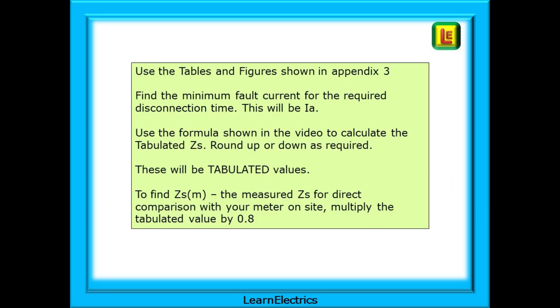Use the tables and figures shown in Appendix 3. Find the minimum fault current for the required disconnection time. This will be Ia. Use the formula shown in the video to calculate the tabulated ZS. Round up or down as required. These will be tabulated values. To find ZSM, the measured ZS, for direct comparison with your test meter on site, multiply the tabulated value by 0.8. And we will leave a link in the description to a video on the 80% values on tabulated ZS and measured ZS.